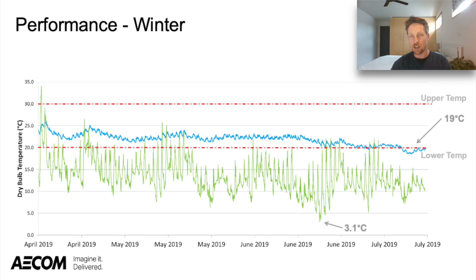The lower temperatures in late winter were actually a result of student holidays. With about 60% of the building occupied, and given the ventilation systems circulate air throughout the whole building, we found that 60% occupation wasn't enough to keep temperatures within that 20 degree band. This was an interesting result, and through building tuning we improved operation by closing down ventilation to spaces unoccupied for longer than 24 hours, which has since improved winter temperatures again.